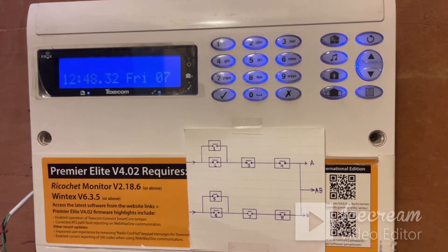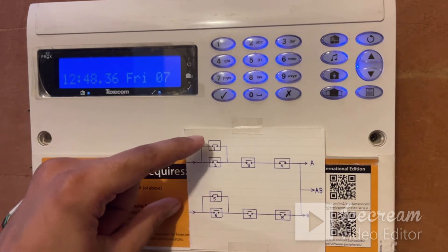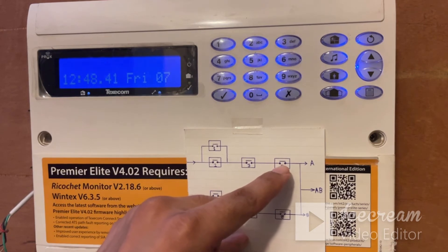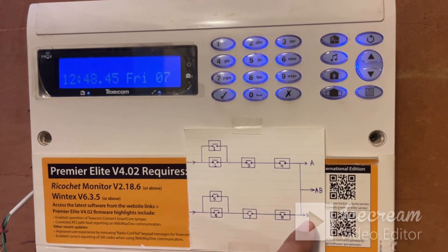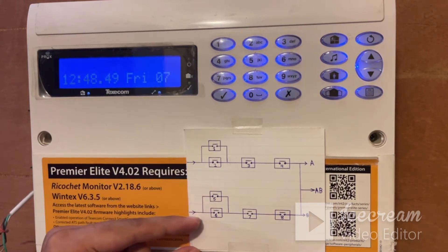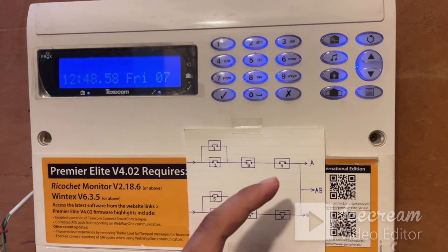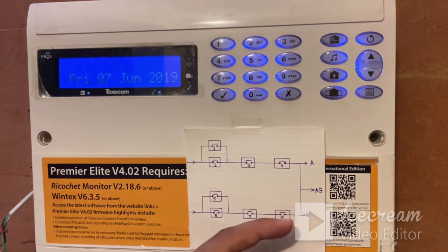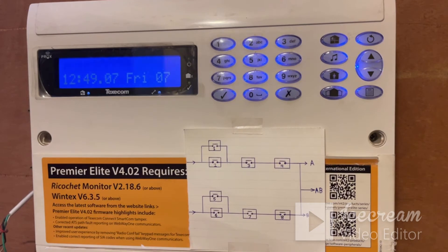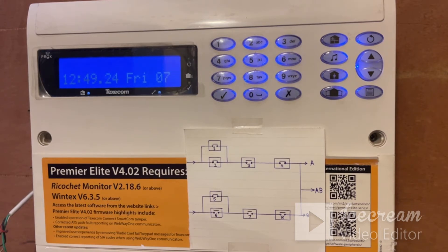When does custom output stage A activate? It will activate when either output 1 or 2, and 3 and 4 are active. Custom output stage B will be activated when either 5 or 6, and 7, and output 8 are active. Custom output stage AB will be activated when either stage A or stage B is active — so there is an OR logic in between.